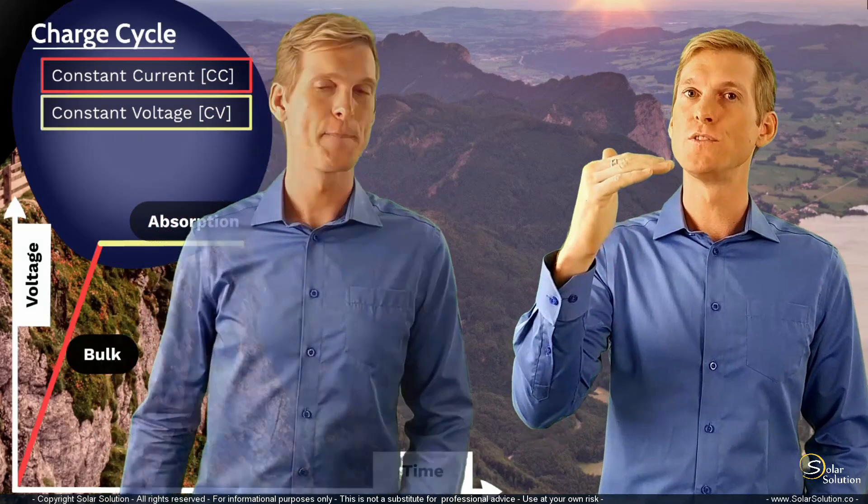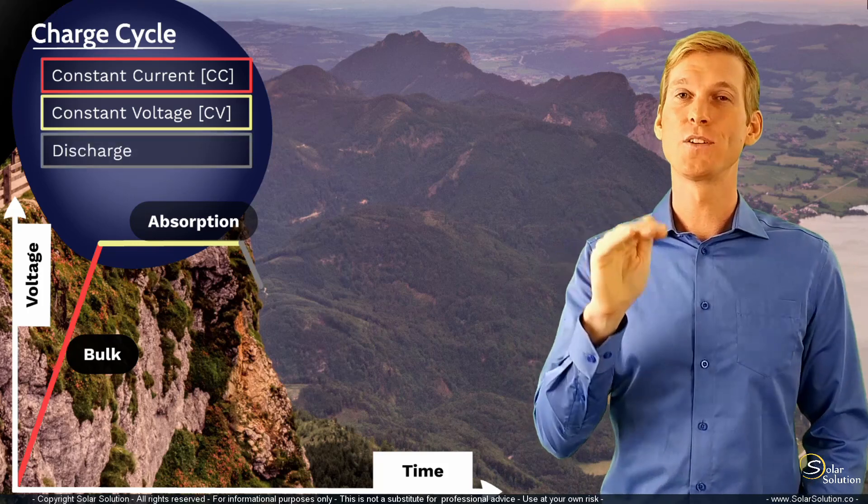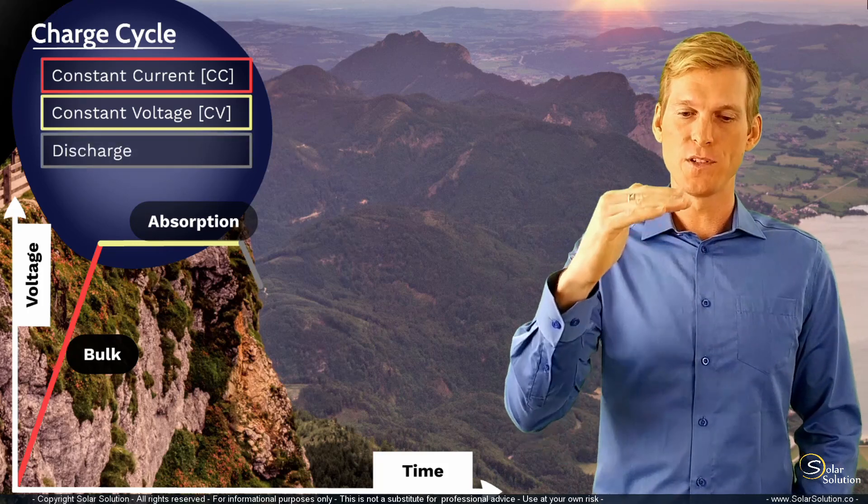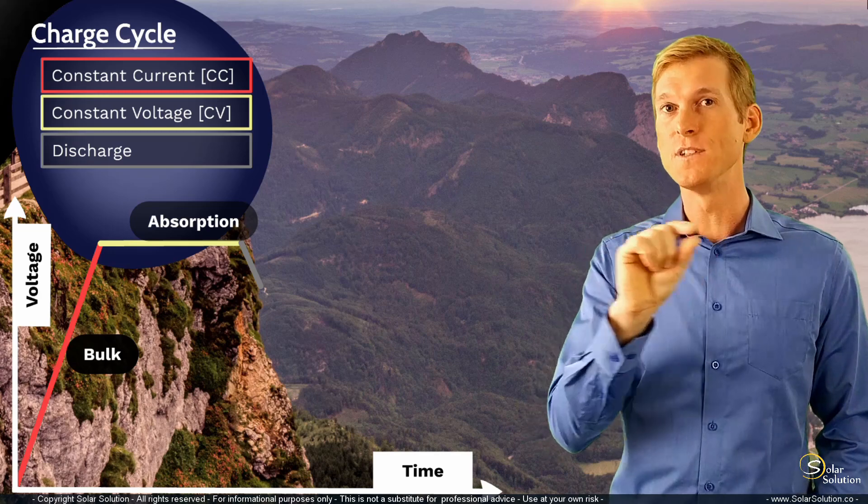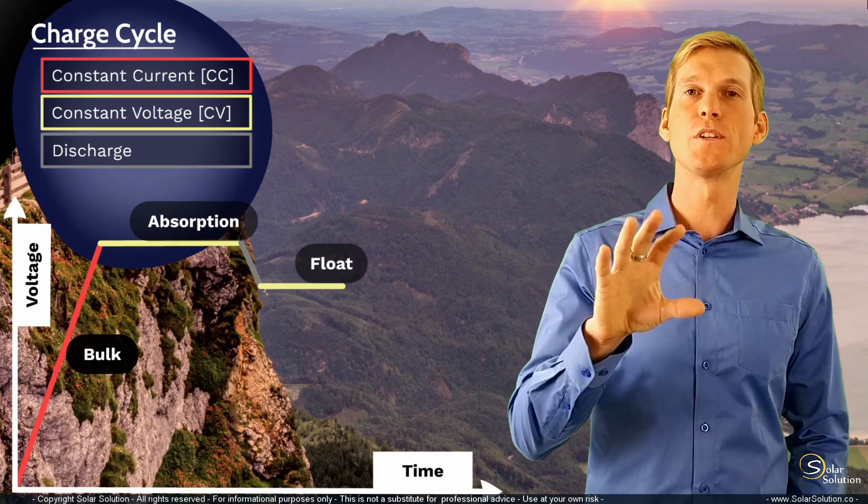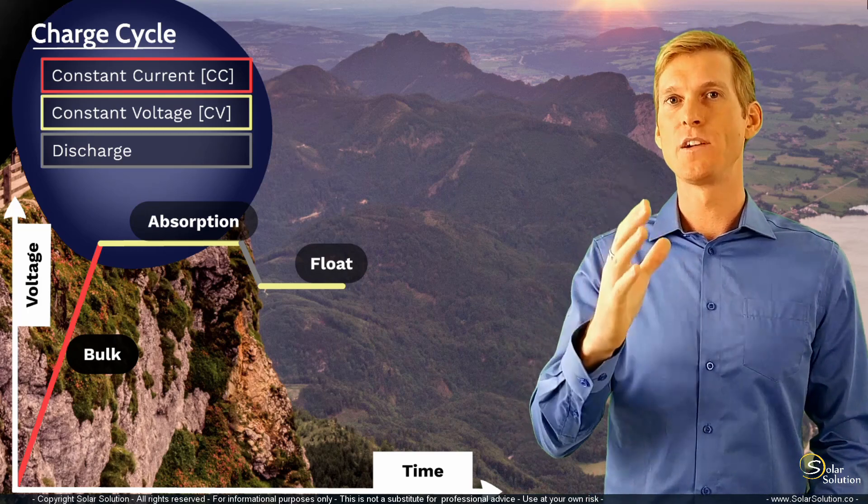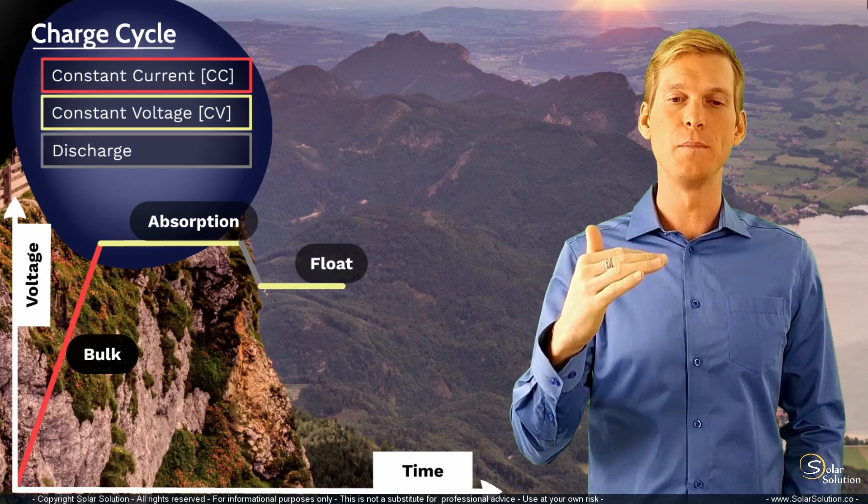And it will now allow the voltage to drop to a lower level, where we are still in the yellow section, so the constant voltage section, but it's just at the lower level, and we refer to this section as the float voltage. Now once you have reached the float stage of the charging cycle, you may assume that the battery is 100% charged, that it is as full as it can possibly be.